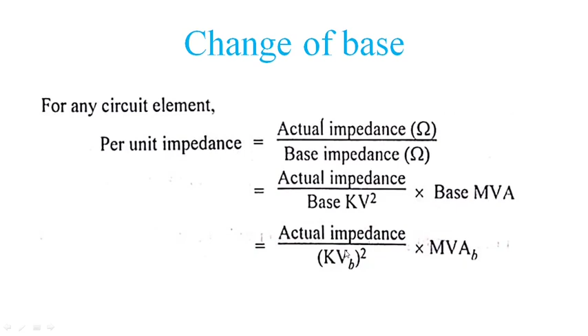So from the given per unit impedance value, we want to calculate the Z per unit new value. The relationship we have already derived in the previous slide is per unit impedance equal to actual impedance divided by kV square into MVA. For a given value, if you modify this, in the previous equation just add the subscript given. That's all. So Z per unit given is equal to Z actual divided by kVB square given into MVAB given.